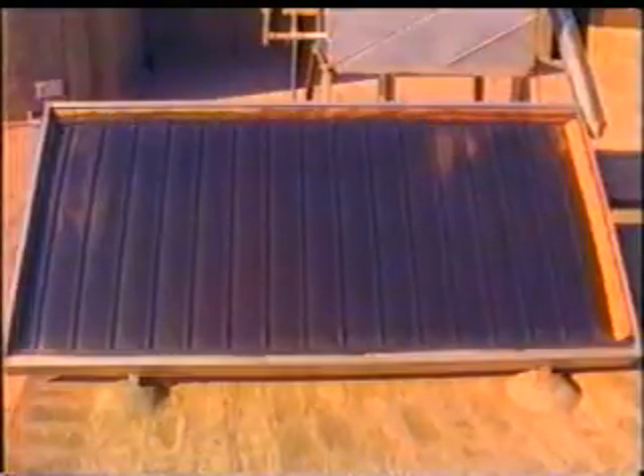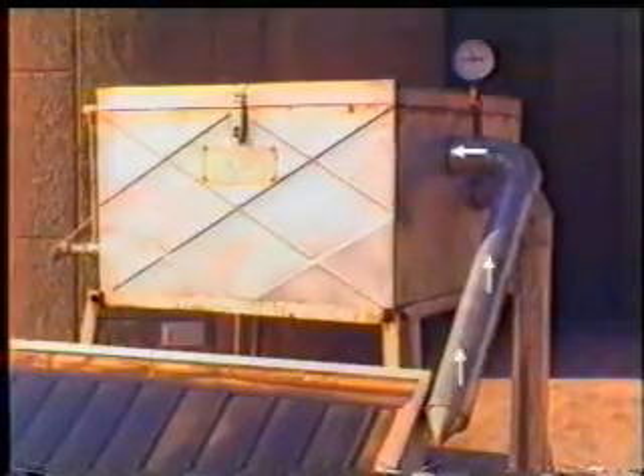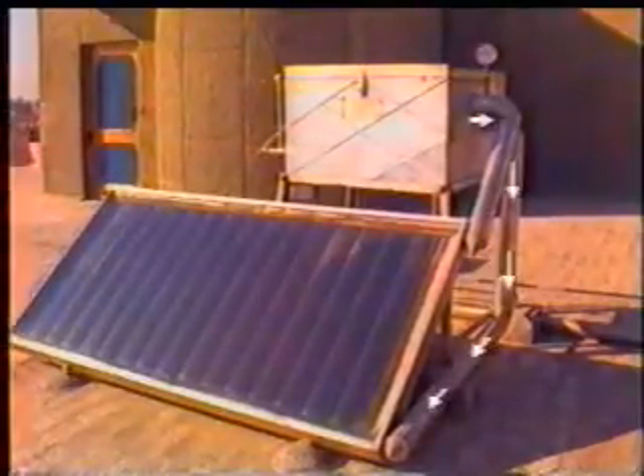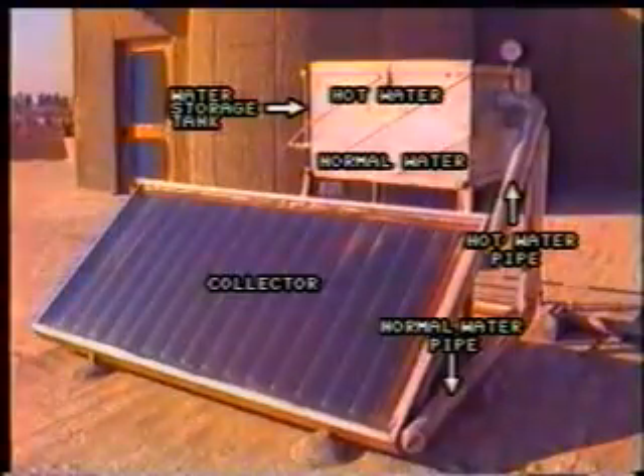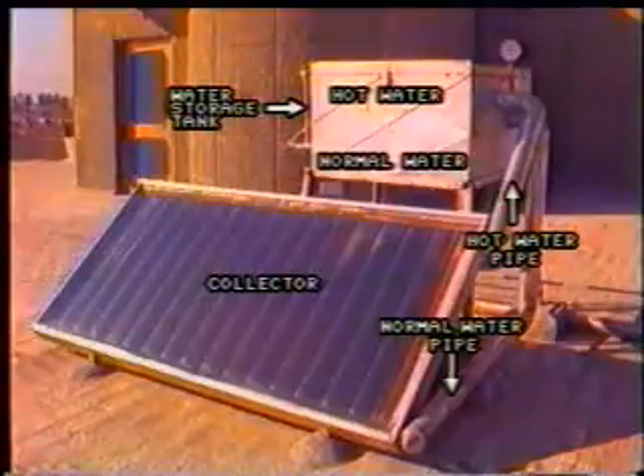Water heated in the collector rises to the tank due to its low density and is replaced by the fresh water from the bottom of the water storage tank. Continuous circulation is thus formed, which heats the entire water. The hot water can be drawn from the hot water storage tank as and when required.